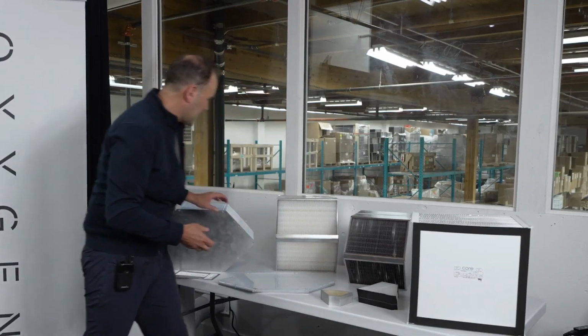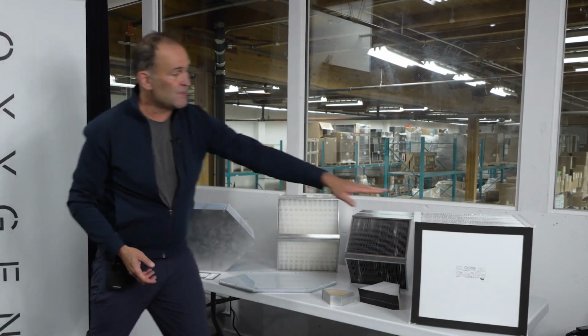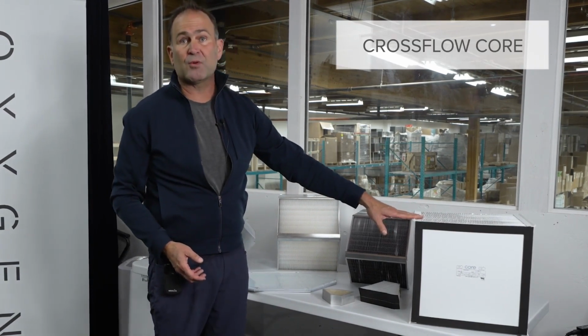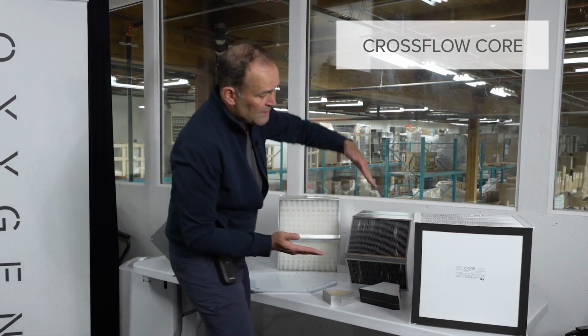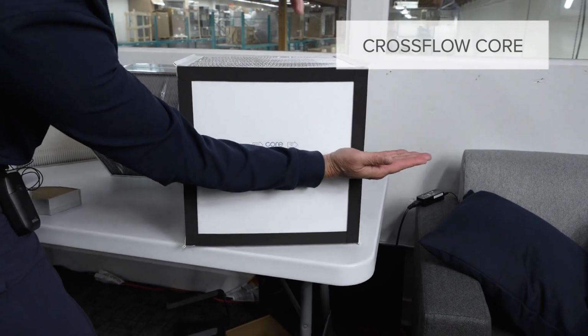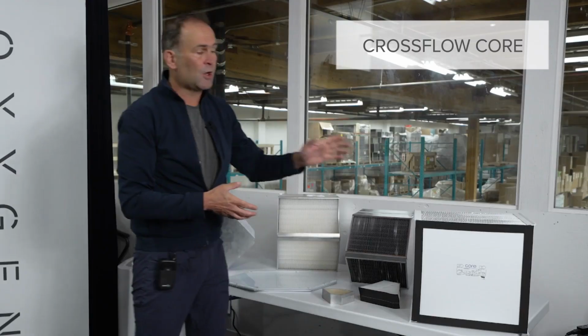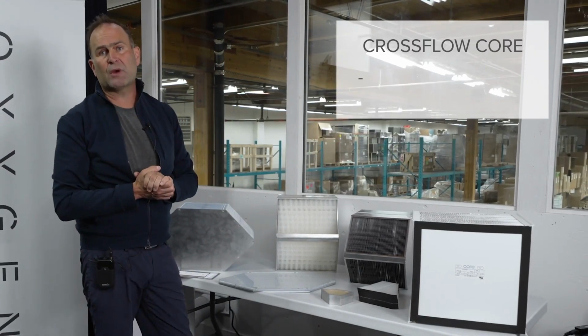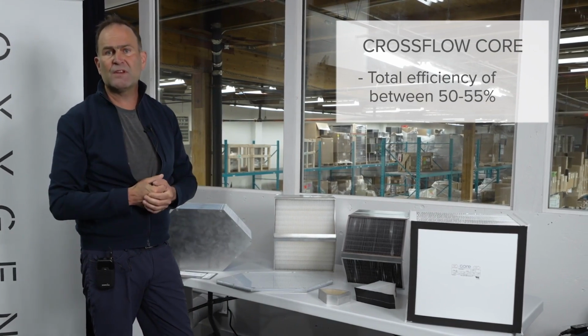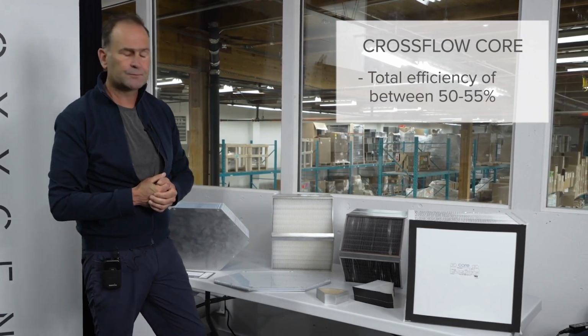You'll also see there's a couple different shapes of cores. This one here is a cross-flow core, and the reason why it's called a cross-flow core is the two air streams are perpendicular to each other. A cross-flow core will typically have a total recovery efficiency of somewhere between 50 and 55%.